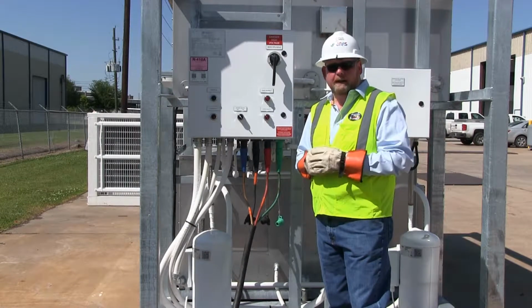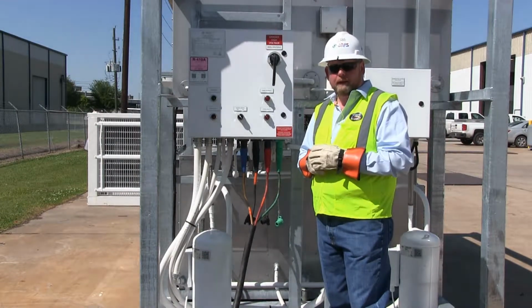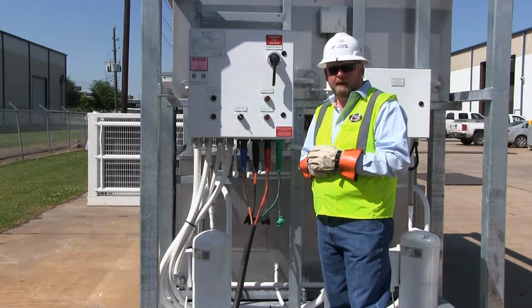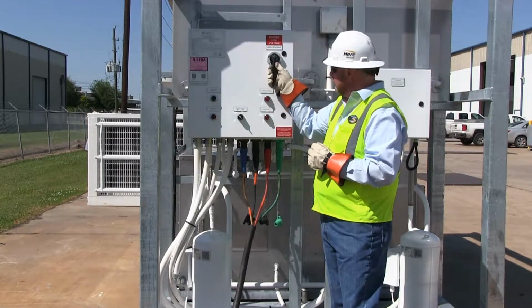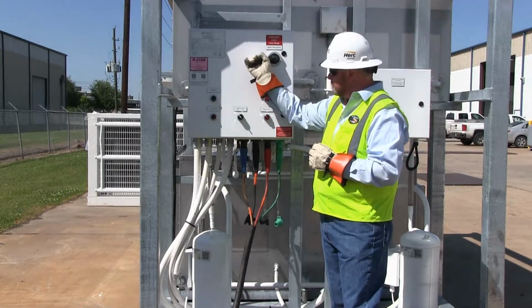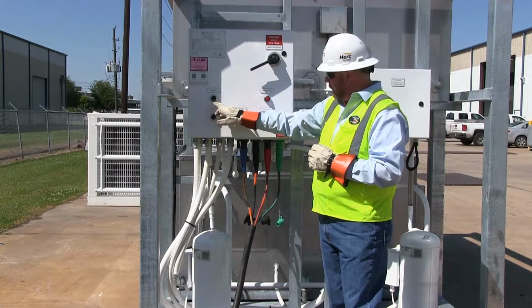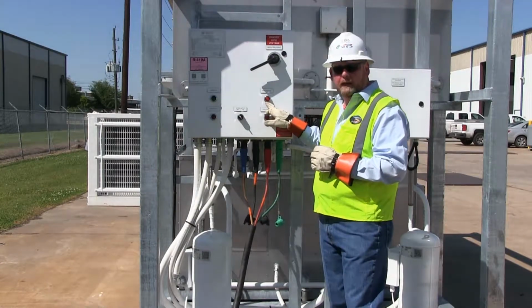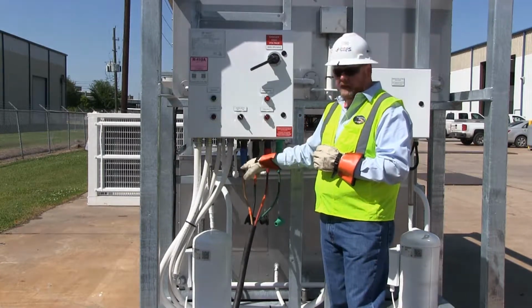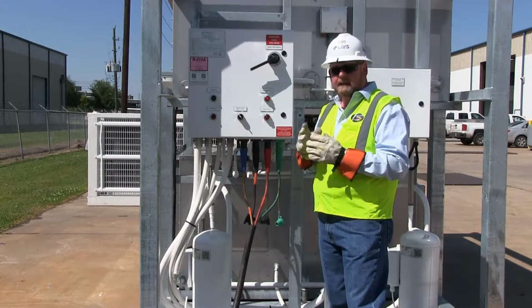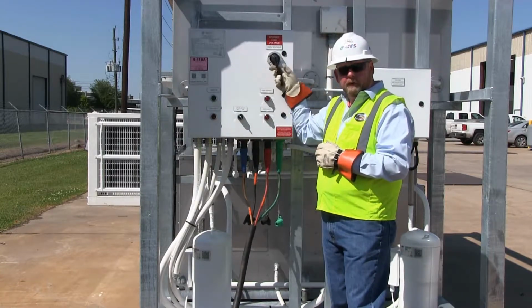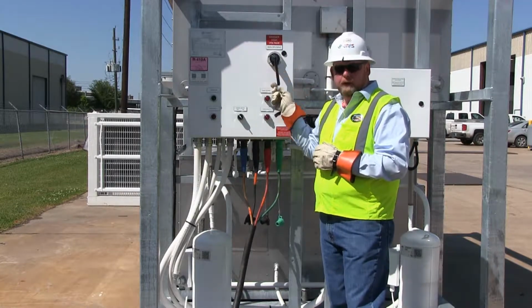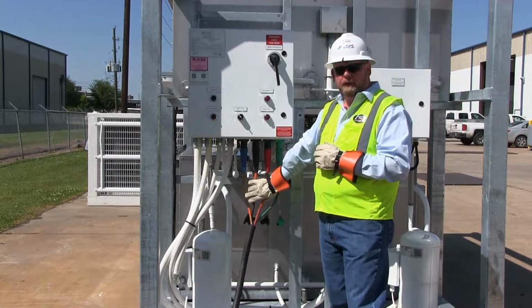We've removed our lockout tagout from our breaker. Now the cam lock cable is energized. We're going to close the main breaker to check for our rotation. Power light came on, but we also have a phase incorrect light that indicates that two of our phases are backwards. We're now going to lock and tag out the breaker and reverse two phases. Please note you never change the cam locks when they're energized.